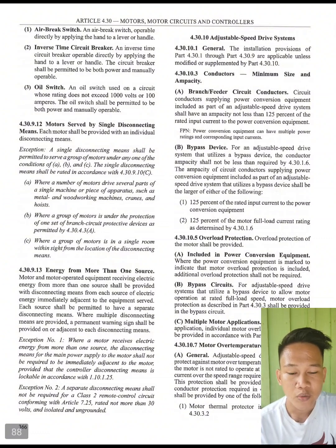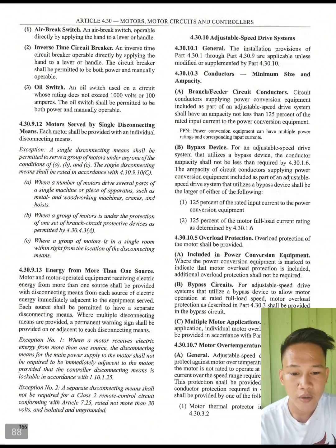4.30.9.10c. So, A, where a number of motors drive several parts of a single machine or piece of apparatus such as metal and woodworking machines, cranes, and hoists. B, where a group of motors is under the protection of one set of branch circuit protective devices as permitted by 4.30.4.3a. C, where a group of motors is in a single room within sight from the location of the disconnecting means.